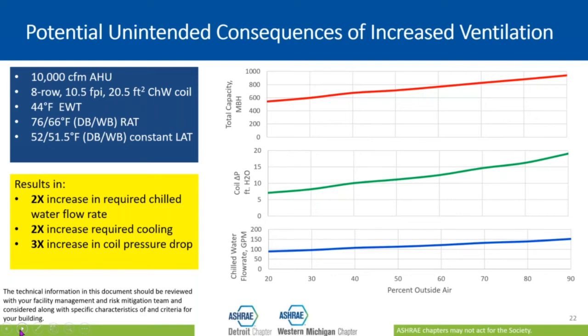This particular graph is showing a very simple system, 10,000 CFM. You can see here the criteria for the system. It's an 8-row coil, 44-degree chilled water temperature, return air temperature 76 dry bulb, 66 wet bulb, and leaving air temperature of 52, almost saturated, right? And with increasing outdoor air percentages, we can see that it just creeps up as we add outside air, right? So we end up with twice the required chilled water flow rate, twice the required cooling, right? So it's very unlikely that the system is going to be able to provide that. But when you're doing your assessment, you want to know how much your system can provide. What's the limit of the equipment that you've got?